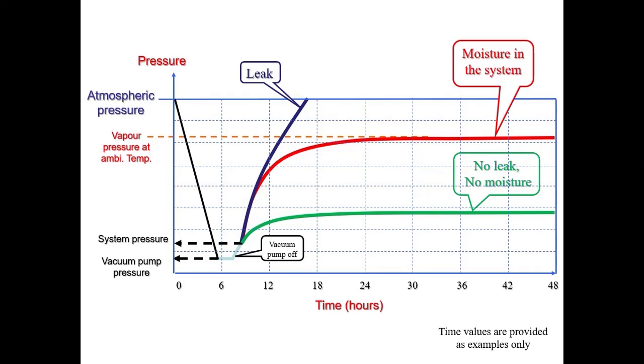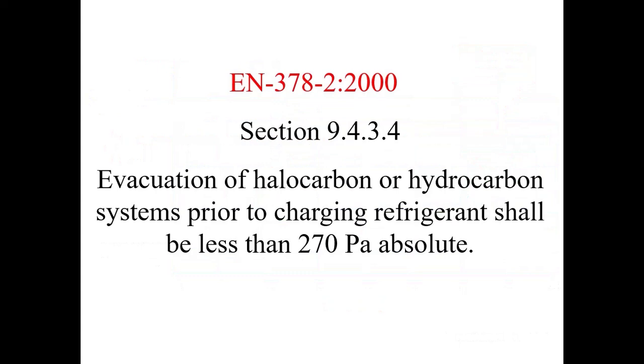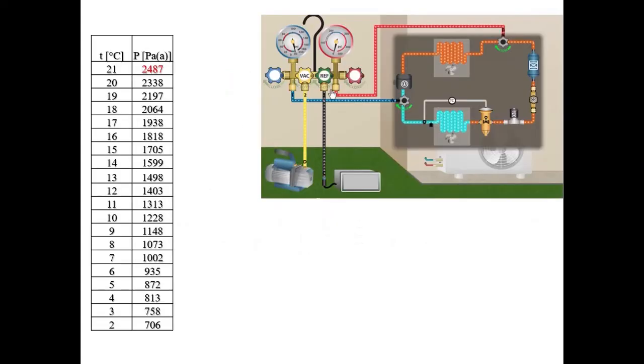In British Standard 378 Part 2, it is stated that evacuation of halocarbon or hydrocarbon systems prior to charging refrigerant shall be less than 270 pascals absolute. Let's see what happens when a large amount of water is present in the system.